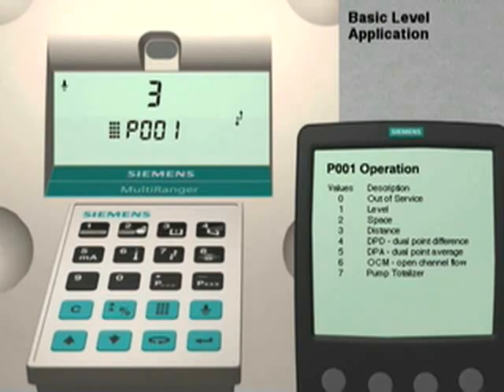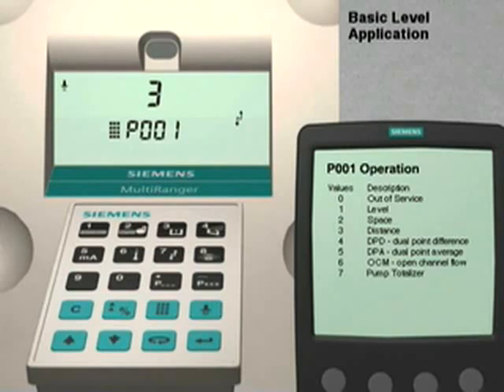Parameter 1 sets the type of measurement for the application. As you can see, it is currently set at 3, which is the factory default value. With this value, the multi-ranger would measure the distance from the transducer to the liquid surface.